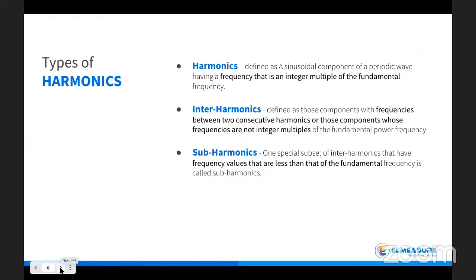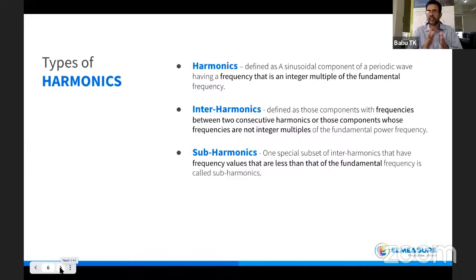Interharmonics are nothing but, between two consecutive harmonics, say second and third, or third and fourth, another harmonic present which has a different frequency. Normally harmonics are integer multiples. This need not be an integer multiple; it will not be an integer multiple. It's in between. The third one that I'm talking about is subharmonics, which also was not heard of 10 years ago, and today it's spoken of much.